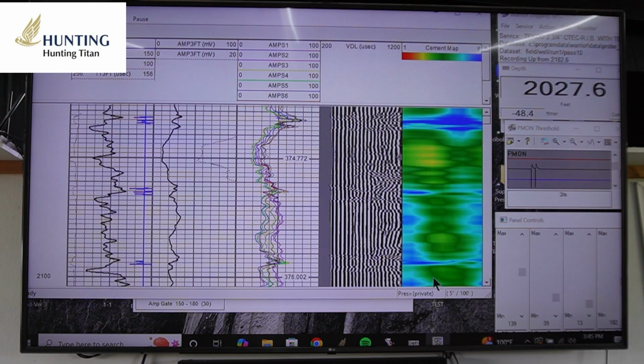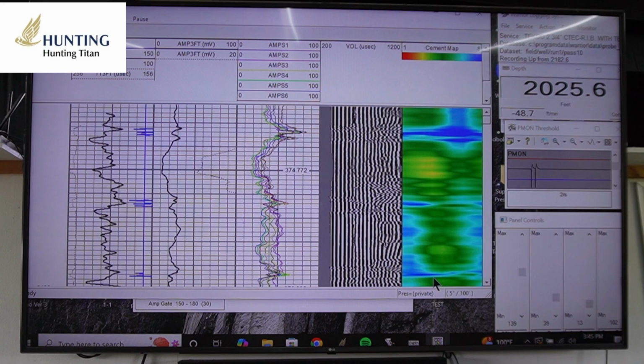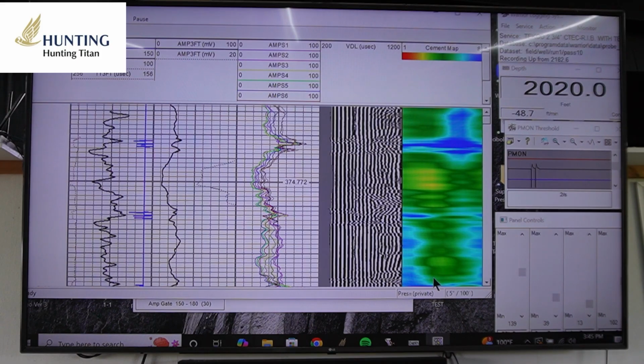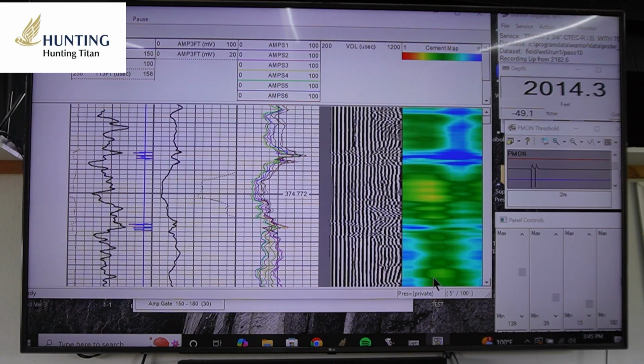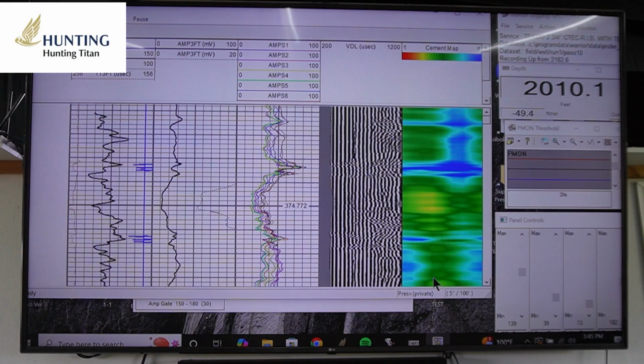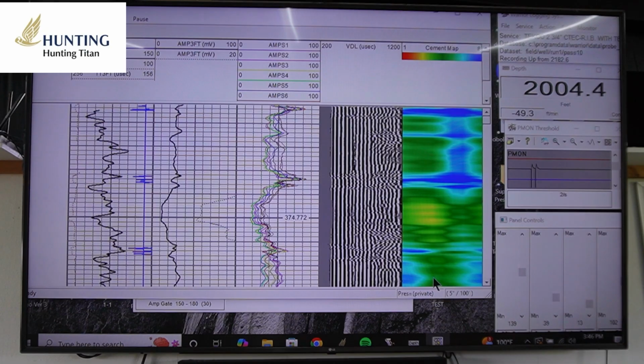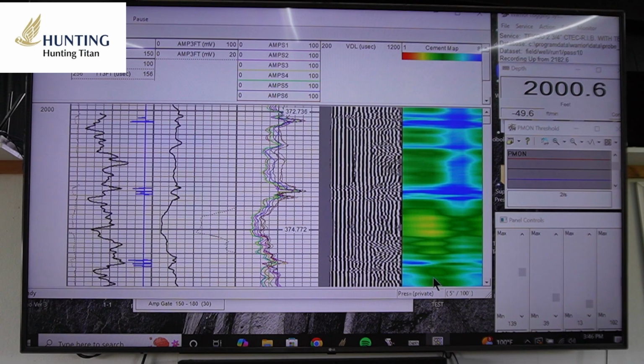Okay, we have now dropped into our cement, the same as what we did with that probe, about 2,000 feet. And I want you to recognize logging up, the sectors are reading a little bit louder, a little higher amplitude than what the probe was. That's why our color map is not reading quite as yellow and green. It's got a little more blue in it. But you'll also recognize that our amp 3-foot is reading pretty much identical to what the probe is.